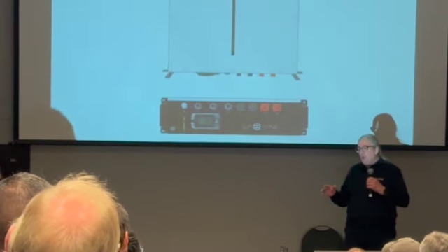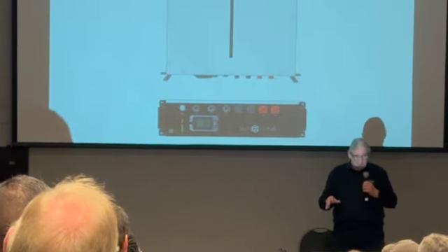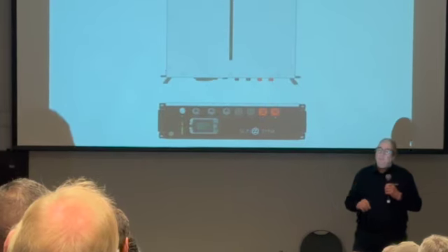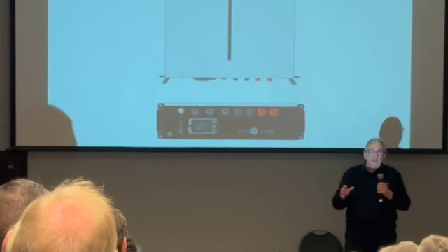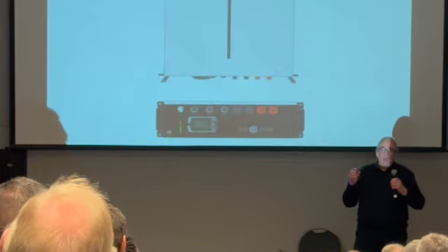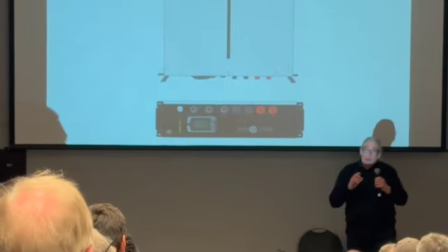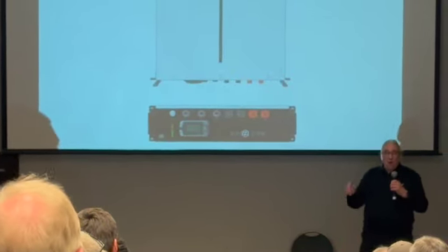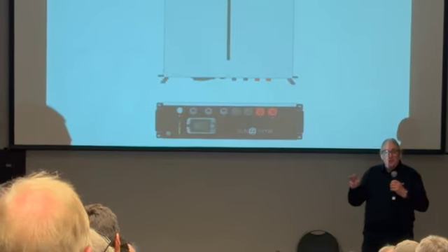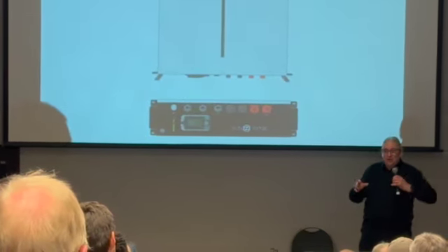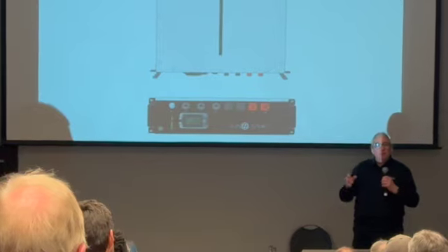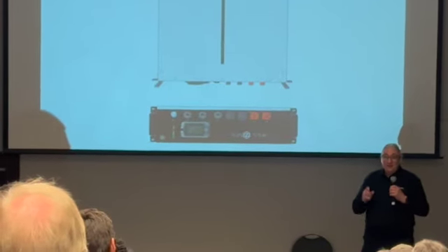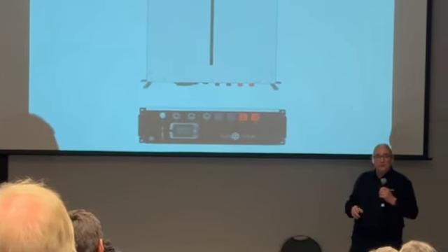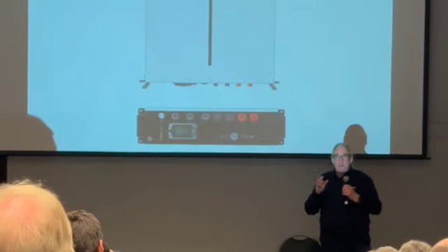I can't comment completely on the regulations here, but I know it's very similar. If you do an installation and try to connect a class 2 inverter, and there are a lot of class 2 inverters in South Africa, onto your house as a UPS, and then suddenly you're in a class that should be class 1, you've got a risk of electrocution. That's a big problem, and a lot of people don't realize that, or the importance of an earth bond.